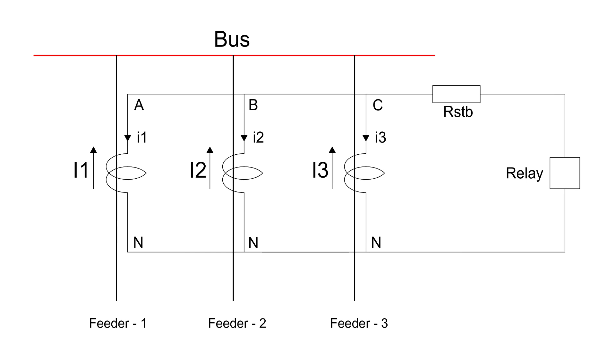Let's assume that high impedance differential protection is used to protect a bus bar as shown in the diagram on the screen. In this protection scheme, all the CTs are connected in parallel and then the four wires A, B, C and N are connected to the relay.